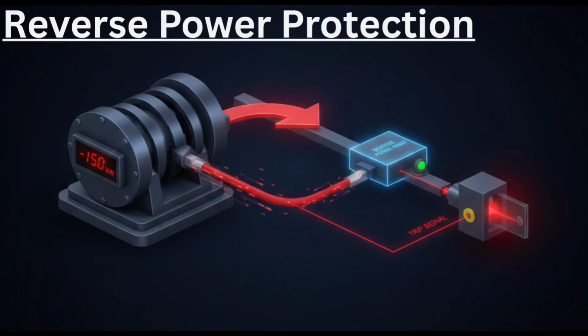Reverse power protection is very important during parallel generator operation. Normally, a generator supplies power to the bus bar. But if the engine fails or fuel supply reduces, the generator may start consuming power instead of producing it. In this condition, the generator acts like a motor. This can damage the prime mover and mechanical coupling.